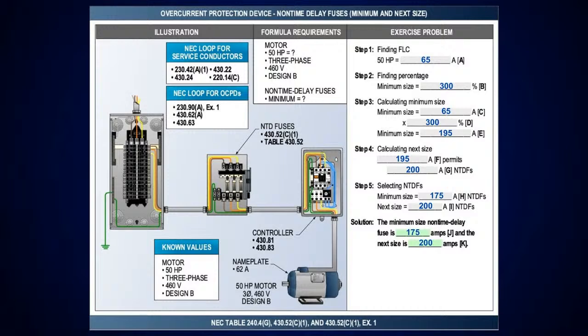Now, you've probably seen some of these arguments on the groups and stuff, and they try to tell you there's no such thing as a minimum. What the minimum is, is a starting point. Okay. And I give a good example of this: if you go over to the 2023 and you look at 440.22(A), they added text in there, and it looks just like motors. And what I always tell everybody is, when you go look at a nameplate, how many times have you looked on there and you have a HACR breaker rating for that AC unit, and it has a minimum and a maximum? That is a terminology that has been used, and we've been doing this forever this way.